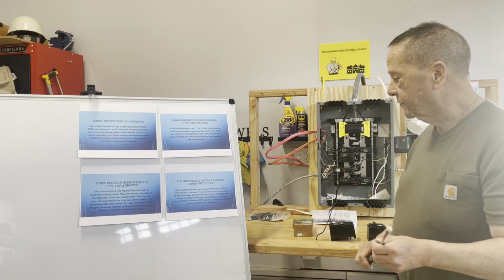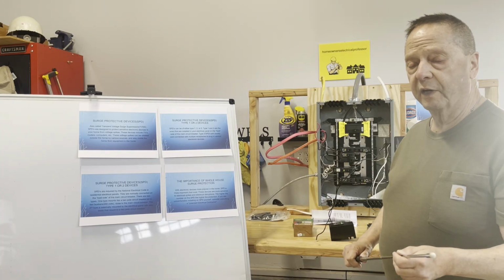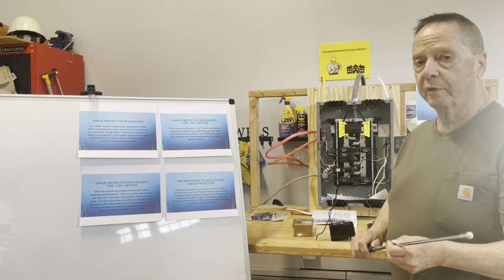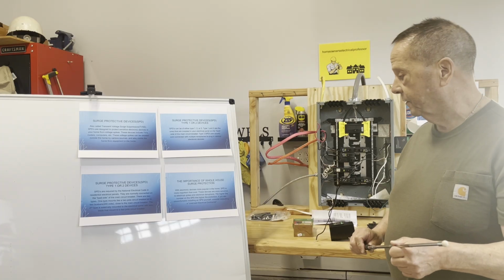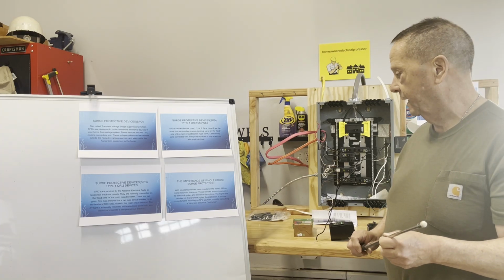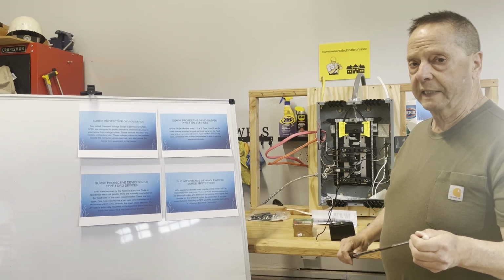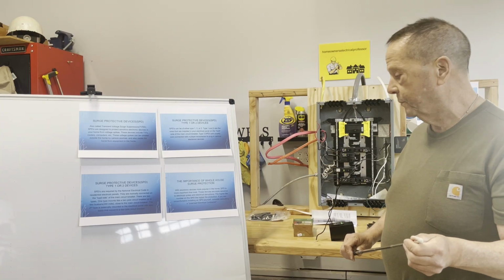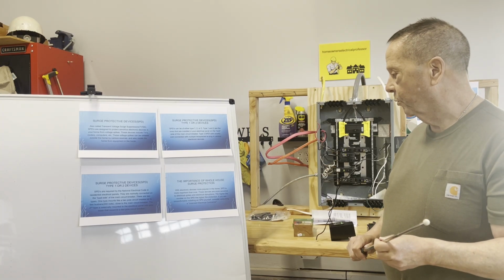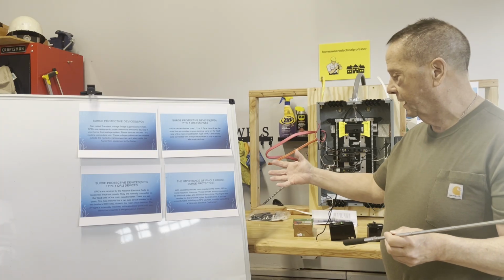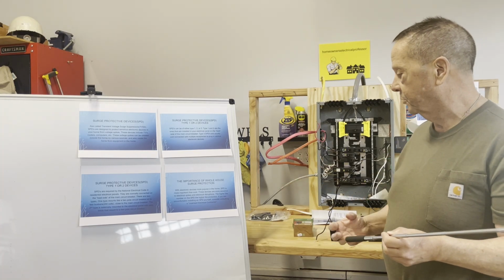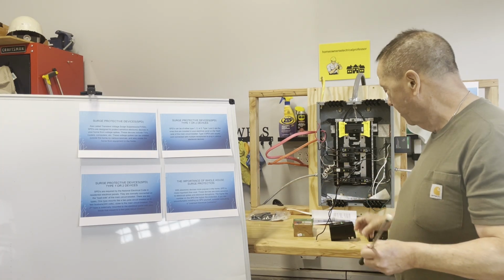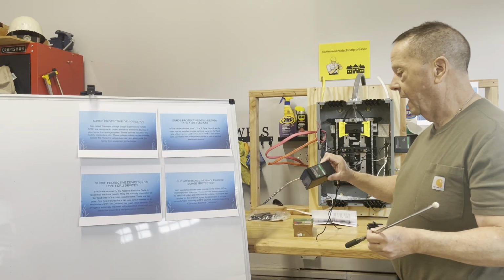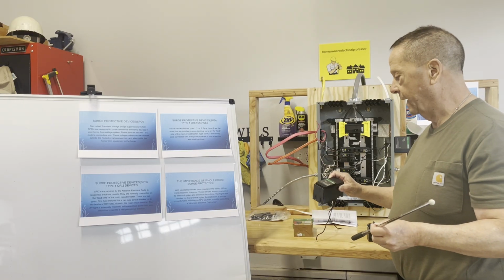The importance of surge protection with electronic devices - they're more popular than ever, and they're also more sensitive to voltage spikes. If anybody's ever had lightning strike near your house, it can wipe things out. These electronic devices today are more susceptible to damage. The higher the number on the SPD, the higher the protection - I'm going to go over that a bit more.